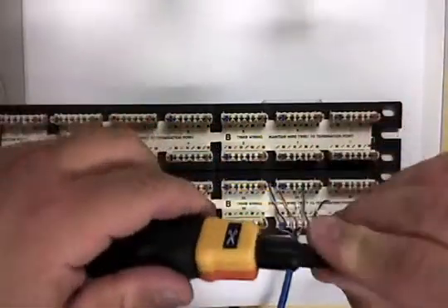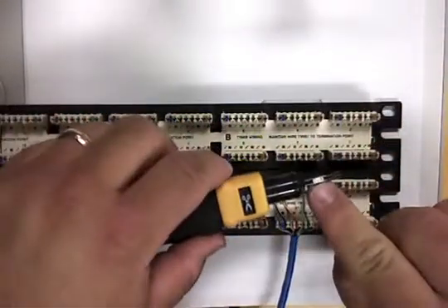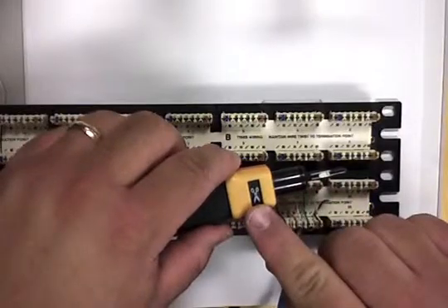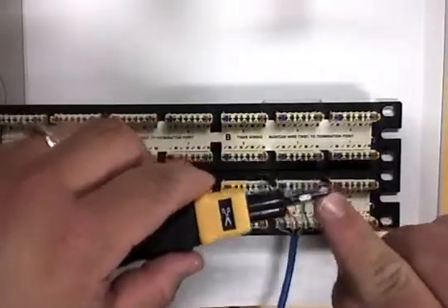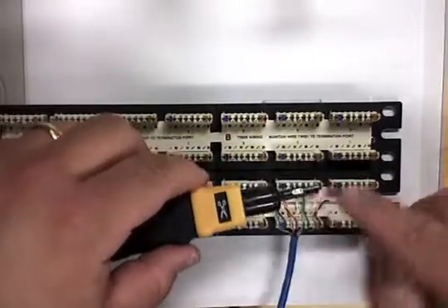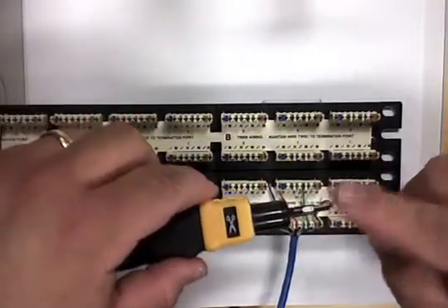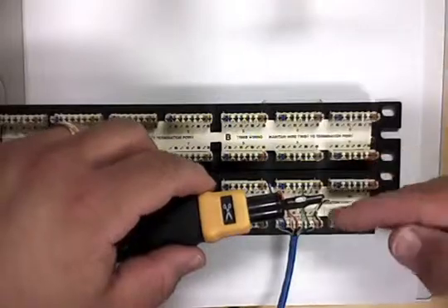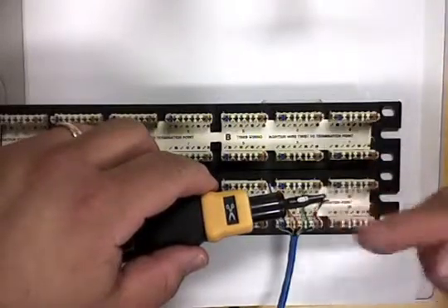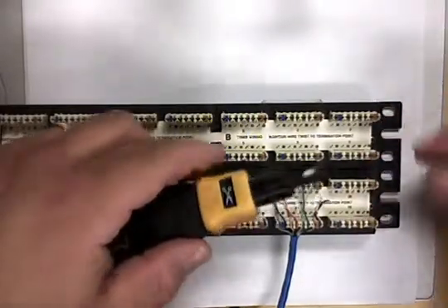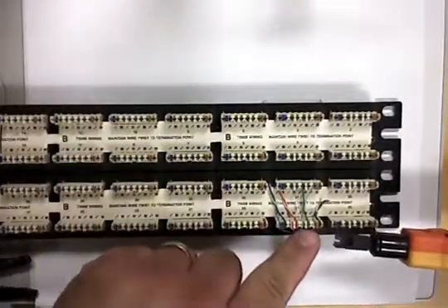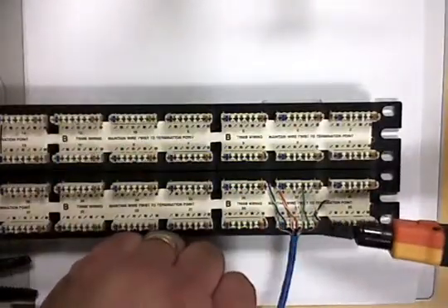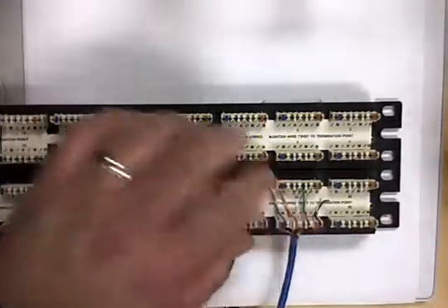I will also notice that the tip is marked with cut side, and there's a little scissor here to remind you that this side of the cutting tool has a little chisel on it to cut the excess wire off. So as I'm punching, I need to make sure the chisel is on the waste side of the wire, the excess side, the side of the wire I want cut off. If I'm not careful and I put that on the wrong side, the chisel cuts the wire off before it gets to the termination point, and you won't have connectivity.